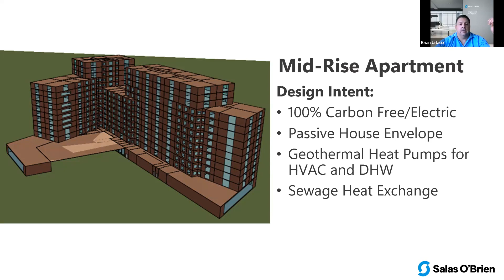So when you think about that sewage heat recovery, you're not going to take a lot of energy out of the effluent because you just don't need it. We need to put it into the effluent as well as the ground loop. So we didn't see as big of a reduction in our ground heat exchanger by adding sewage heat recovery because we just don't have the heating load.